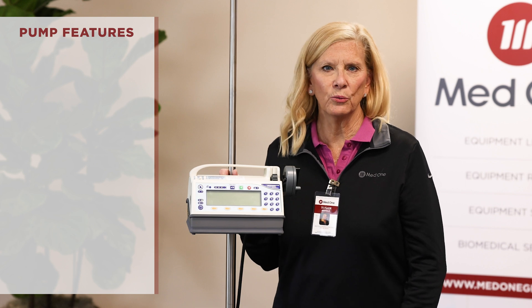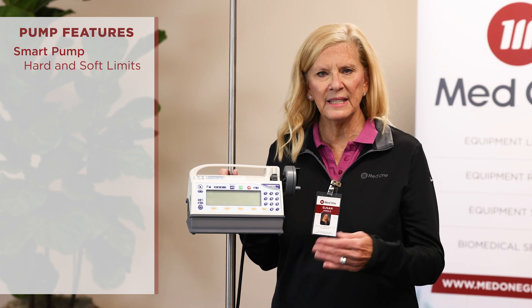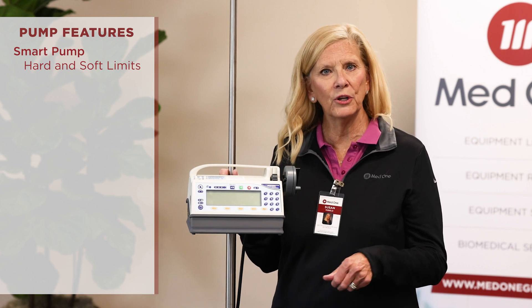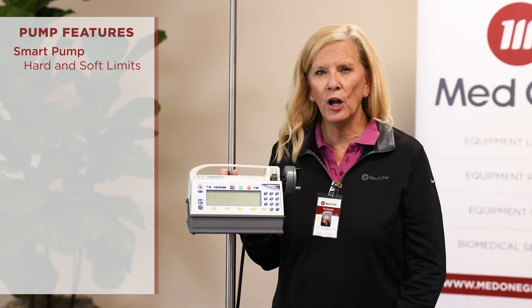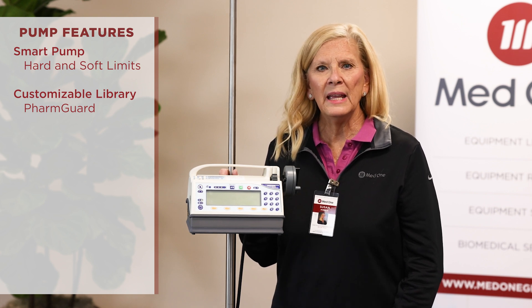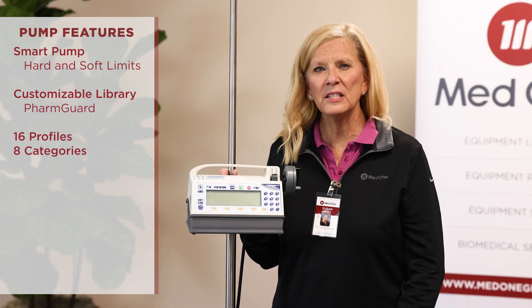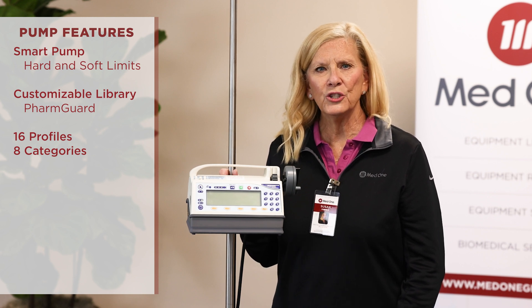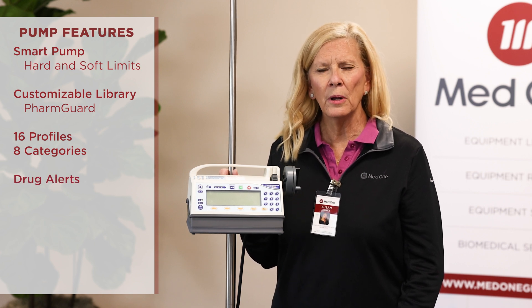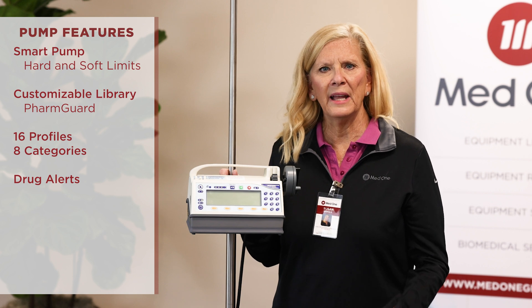The MedFusion 4000 is a smart syringe pump with hard and soft limits, so if you make a mistake you can say no, or if you need to override you can say yes. It also has hard limits where you can't give that dose and have to go back and reprogram. It has a customizable library called PharmGuard software that you can customize and build to your hospital's formulary. It has 16 profiles — such as pediatrics and ICU — and eight categories, which are basically speed keys or shortcut keys that get you to sections of the alphabet much quicker to save time in programming. It also has drug alerts, which are like a post-it note to the nurse for a specific protocol, such as two-RN checks or use a filter.